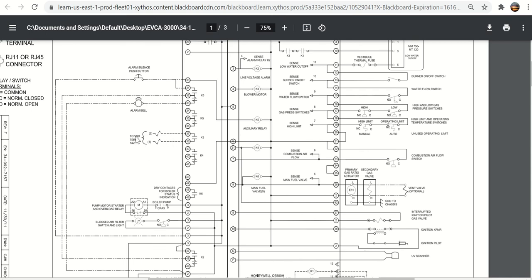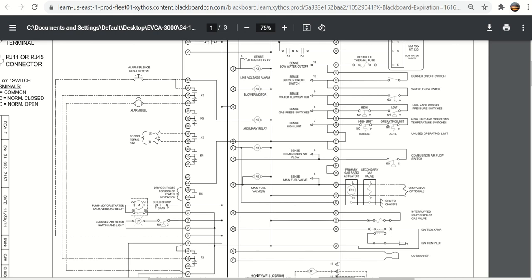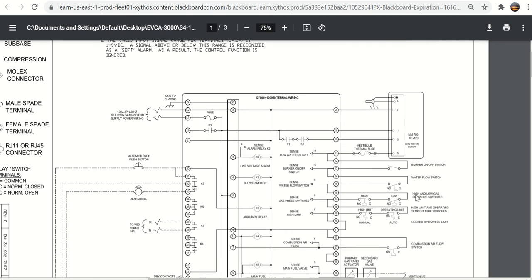Here's the VSD terminals, VSD, VFD. Some people say variable frequency drive. Some people say variable speed drive. VSD, VFD means the same thing. That's the terminal that would actually start that, K3. You see here K3 is the blower motor. Contacts for K3 right there tell the VFD to close.